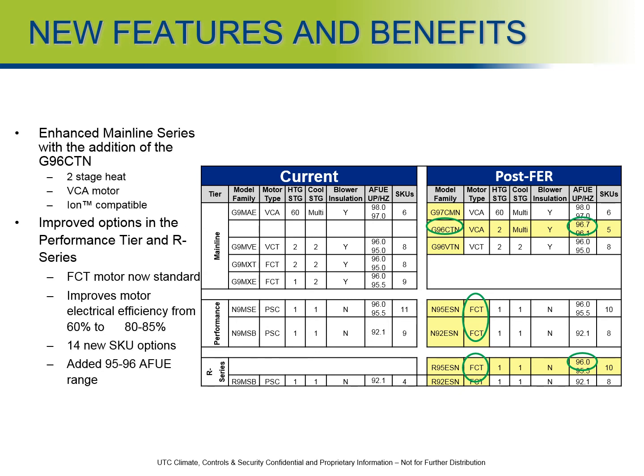The signal to the motor is a pre-programmed speed signal sent from the control board, and that signal stays constant based on what mode the system is in and the pre-programmed algorithms in the control board. Essentially it acts very similar to an X13 motor. However, you have many more speeds and a larger speed range capability with that variable speed constant torque motor than you would with, say, an X13 motor.